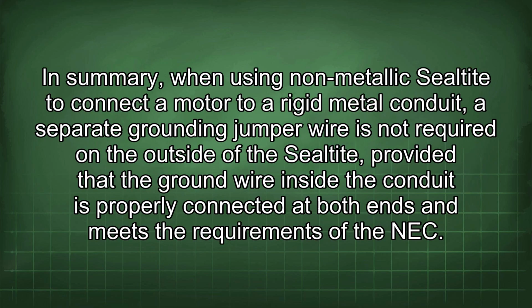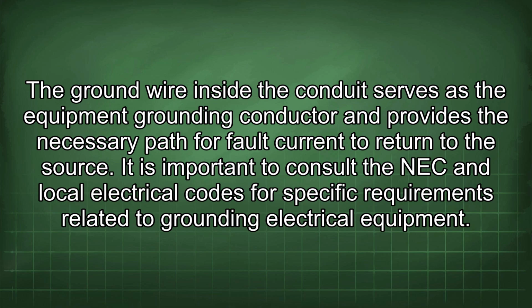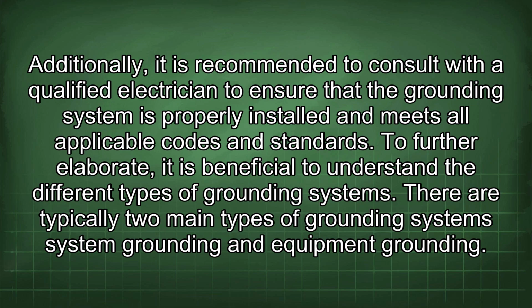In summary, when using non-metallic Sealtite to connect a motor to a rigid metal conduit, a separate grounding jumper wire is not required on the outside of the Sealtite, provided that the ground wire inside the conduit is properly connected at both ends and meets the requirements of the NEC. The ground wire inside the conduit serves as the equipment grounding conductor and provides the necessary path for fault current to return to the source. It is important to consult the NEC and local electrical codes for specific requirements related to grounding electrical equipment. Additionally, it is recommended to consult with a qualified electrician to ensure that the grounding system is properly installed and meets all applicable codes and standards.